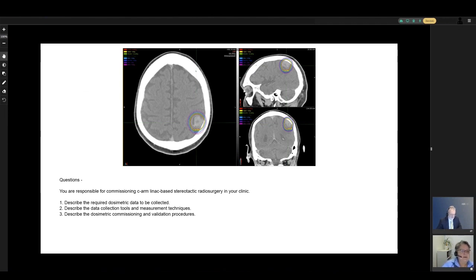So when you talk about LINAC-based SRS and the dosimetry data, you really need to worry about small field dosimetry. So this includes the PDD, profiles, output factor. All of these need to be measured with at least 2 different devices. And each of these devices needs to be appropriate for small fields. So you want to use something like a diode, an edge detector, a diamond detector, or a micro ionization chamber.